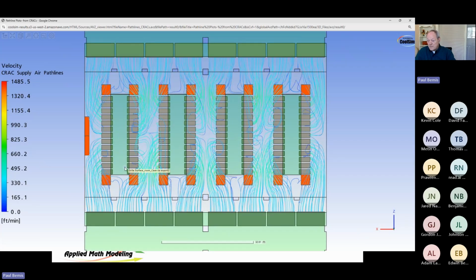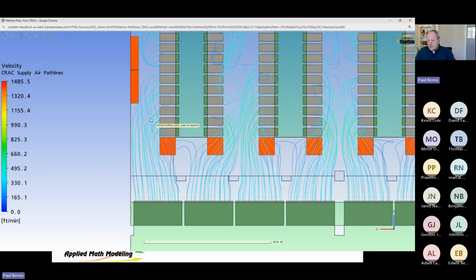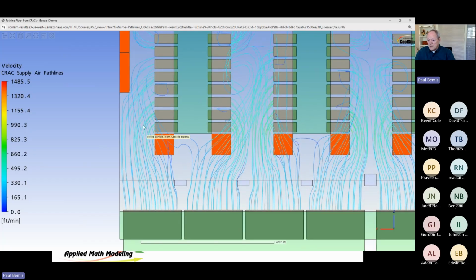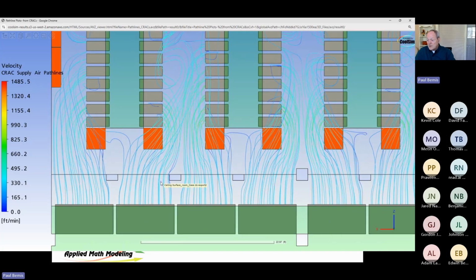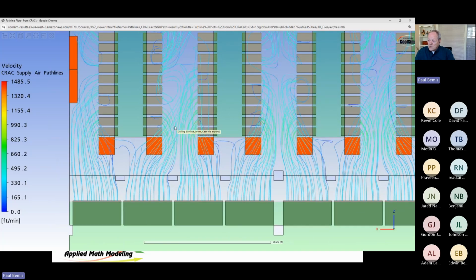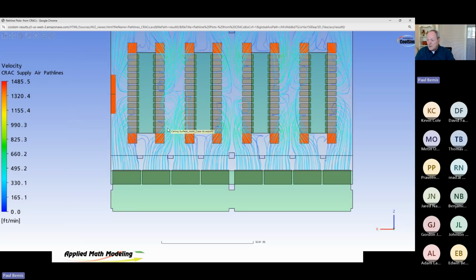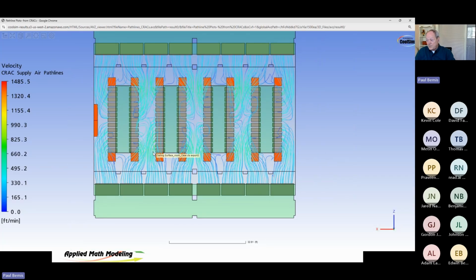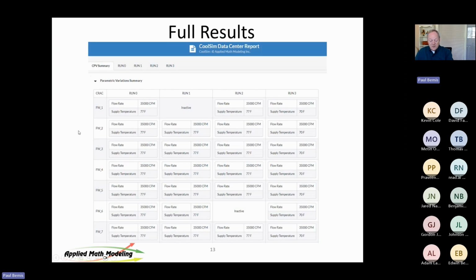This is velocity. I have a lot of velocity happening right in this area. Look, we're pushing up into 900 feet per minute, going to these servers. It has to come around this corner. Geometry makes a difference. Here the air has to come around this corner and come in. The velocity is going to be high here. And it shows up in leakage. So I'll show you the leakage. We have thermal cut planes on this.